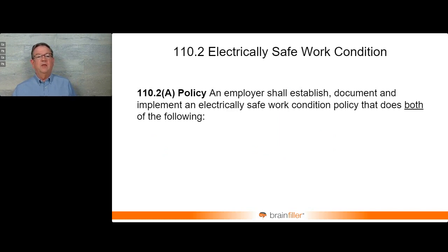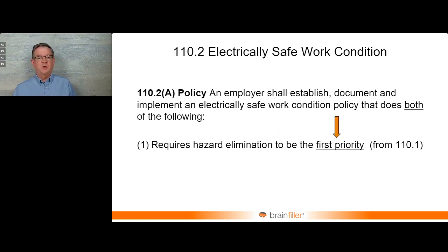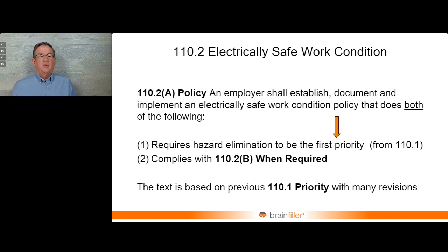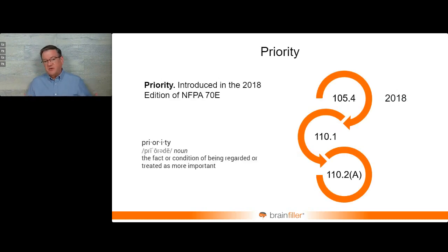The policy must have hazard elimination as the first priority, and then it defines when this is required. The priority, as I said, was first introduced in 2018. First priority, eliminate the hazard, and it's been there since 2018. It just keeps getting moved around. It used to be in 105, then it went to 110.1, the very first part, but then it had to get bumped a little bit, since 110.1 is now going to be the scope.